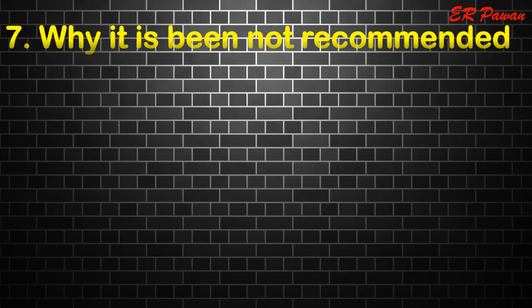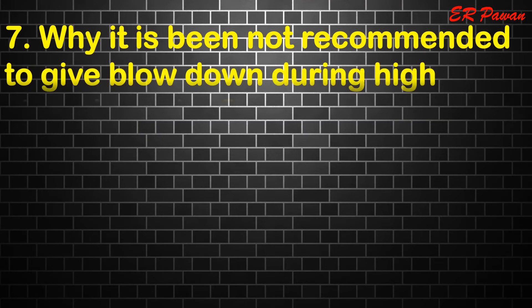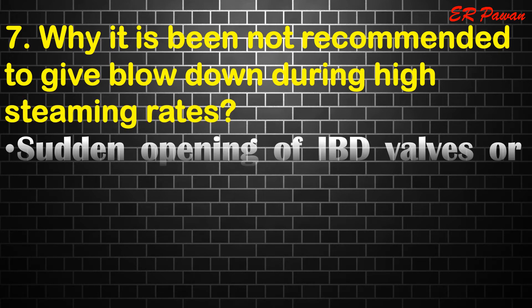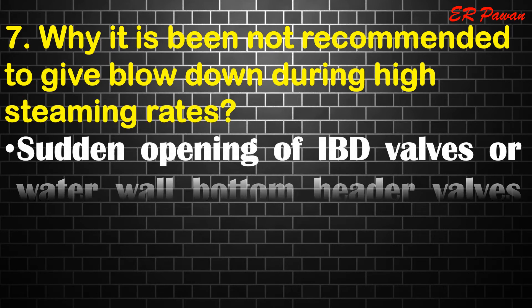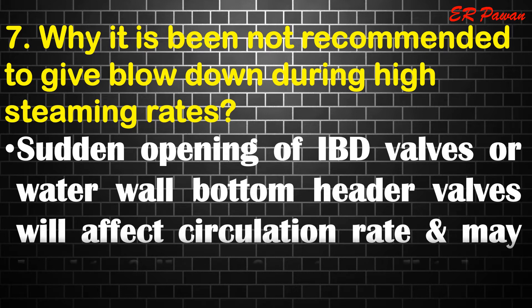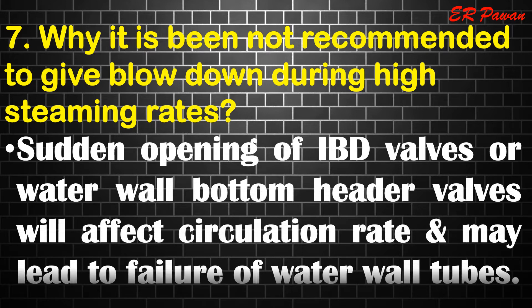Question 7: Why is it not recommended to give blowdown during high steaming rates? Sudden opening of IBD valves or water wall bottom header valves will affect circulation rate and may lead to failure of water wall tubes.